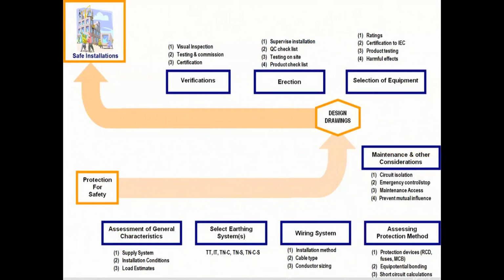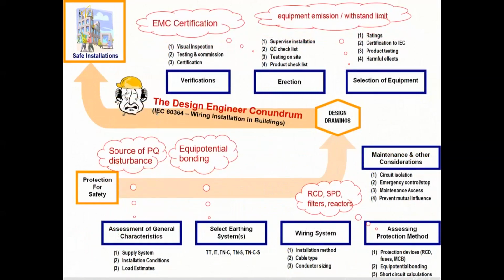Now, the design engineer conundrum. How do you deal with PQ? This is a roadmap every design engineer must know. You cannot say you don't know. This roadmap is actually from part 1 to part 8 of the IEC 364. How you do design, you assess, and then finally you do verification. The end result is the safe installation. So that's where PQ comes in.